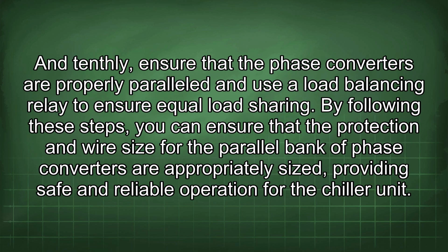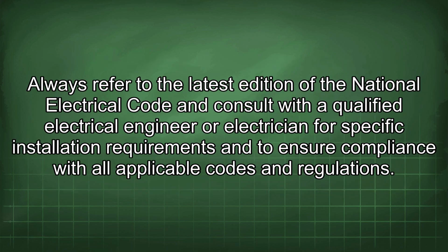Ensure that the phase converters are properly paralleled and use a load balancing relay to ensure equal load sharing. By following these steps, you can ensure that the protection and wire size for the parallel bank of phase converters are appropriately sized, providing safe and reliable operation for the chiller unit. Always refer to the latest edition of the National Electrical Code and consult with a qualified electrical engineer or electrician for specific installation requirements and to ensure compliance with all applicable codes and regulations.